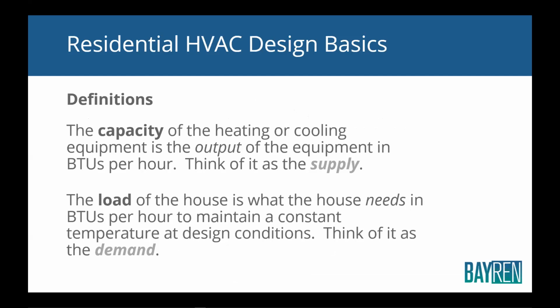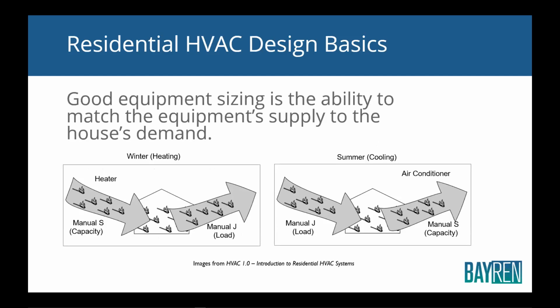Think of capacity as the supply, what you're getting from the equipment. And the load, think of that as the demand of the house. So you've got supply and demand. So the ability to properly size equipment is the ability to match the capacity to the load. So in the winter, you're matching the capacity of the heater to the rate that the heat is leaving. And in the summer, you're matching the ability of the air conditioner to extract heat from the rate that is coming in. Okay, so that's what properly sizing equipment is all about.